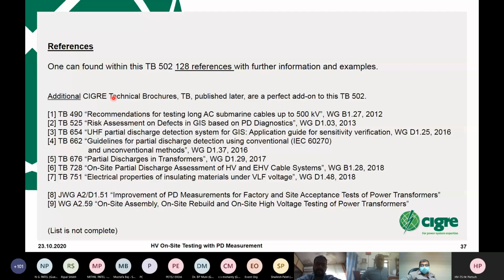In addition, over the years there were some additional technical brochures I'd like to mention: testing of long submarine cables, published the same year, and one year later a technical brochure about PD analysis and risk assessment on GIS. The different defects are described there, along with the UHF PD measurement technique again in GIS, and here the sensitivity verification, which I briefly mentioned, is applied in detail.